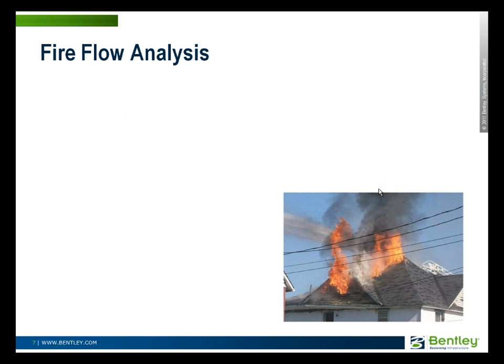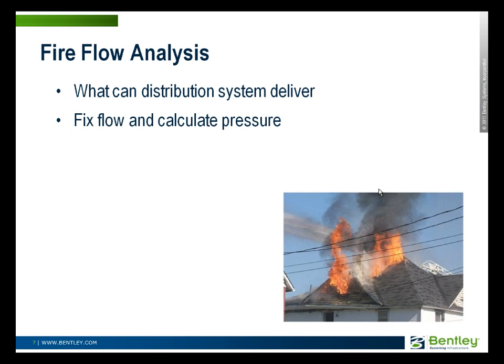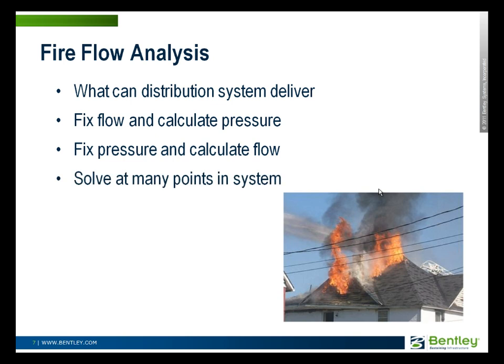Fire flow analysis is one of the most widely used tools in water distribution system modeling. It basically asks the question: can the water distribution system deliver the flows that are needed for firefighting? These vary in different parts of the world — some have very high requirements in North America and lower ones generally in other parts of the world. You can approach this two ways: you can set what flow you want and see if you have enough pressure, or you can set the pressure you want and the model will calculate what flow can be delivered at that residual pressure. The tools in WaterGems and WaterCAD can solve for this all over the system, going node by node to figure out how much water can be delivered at every point in one run, rather than having to make hundreds of individual runs of the hydraulic model.